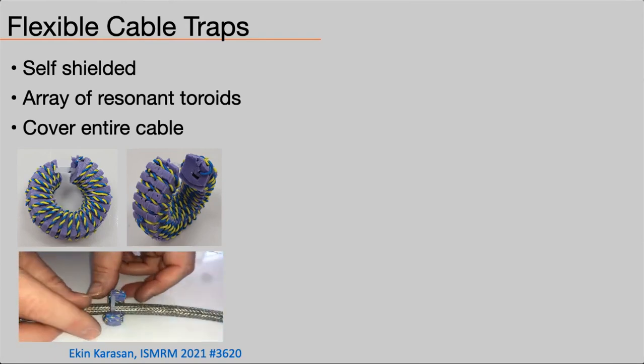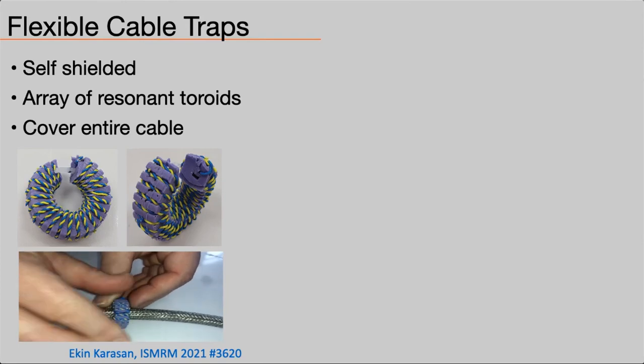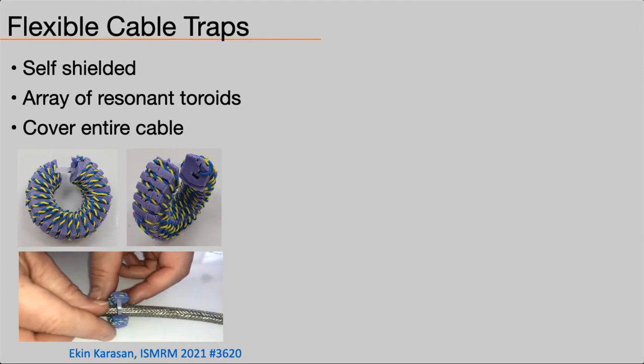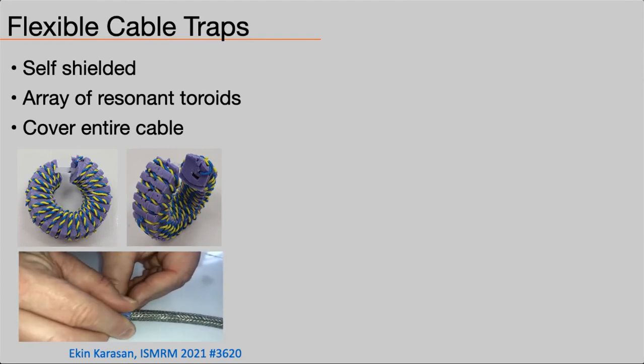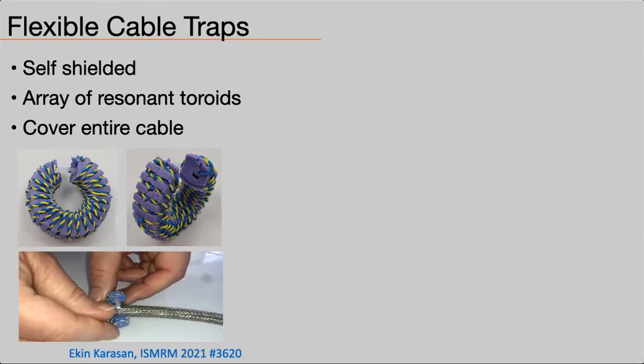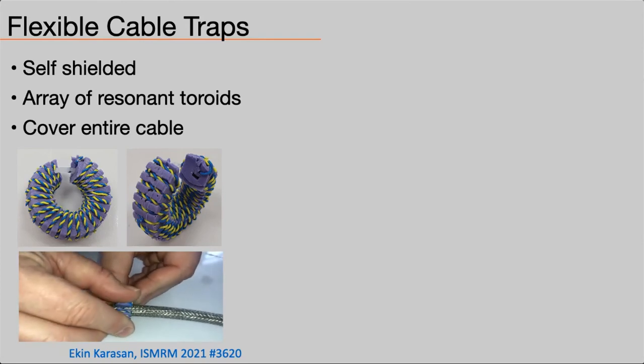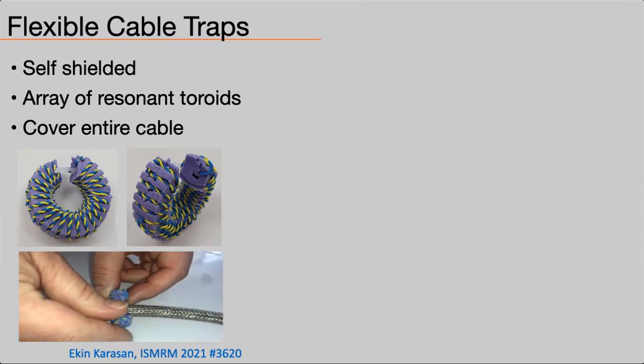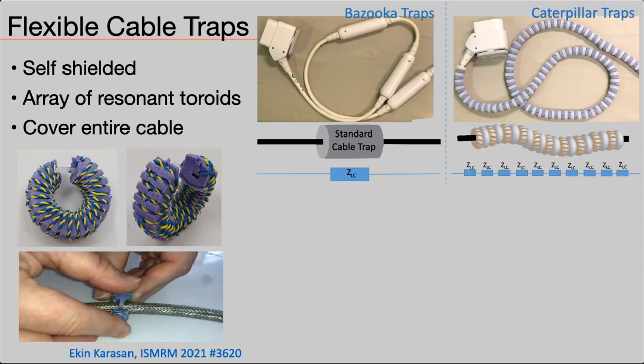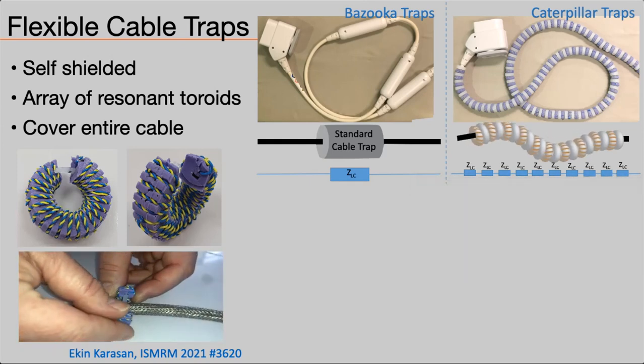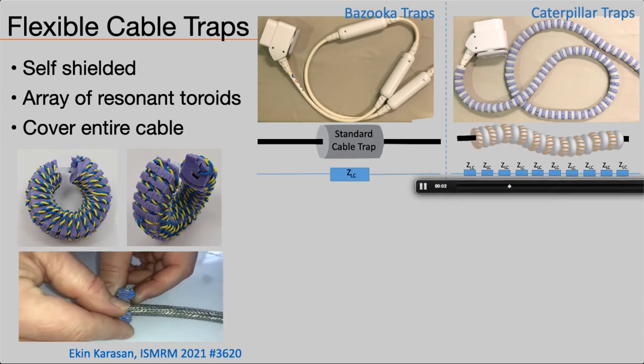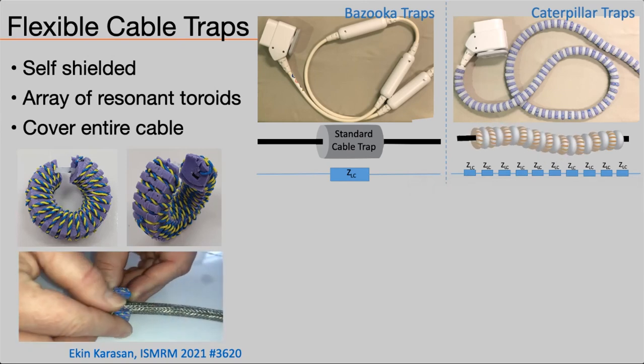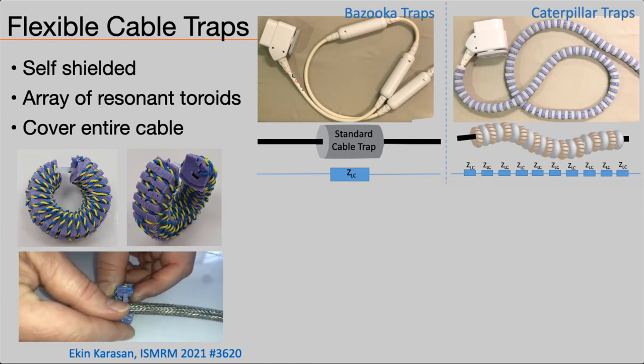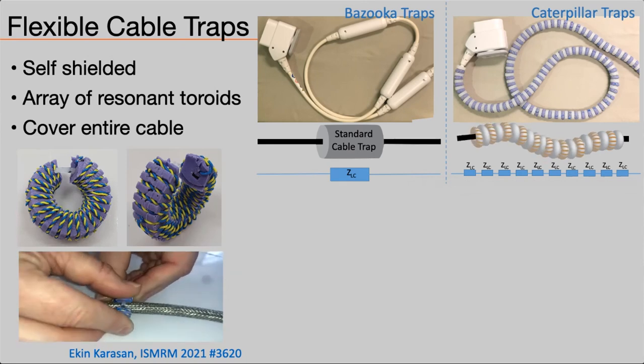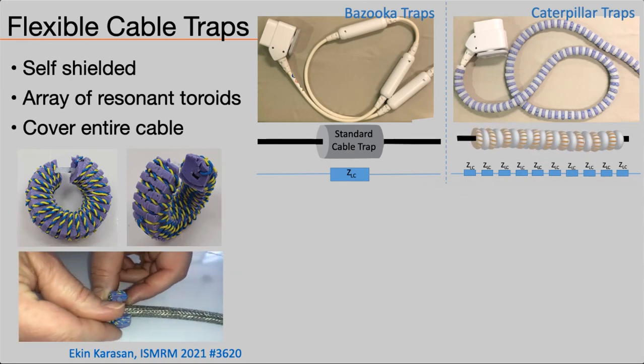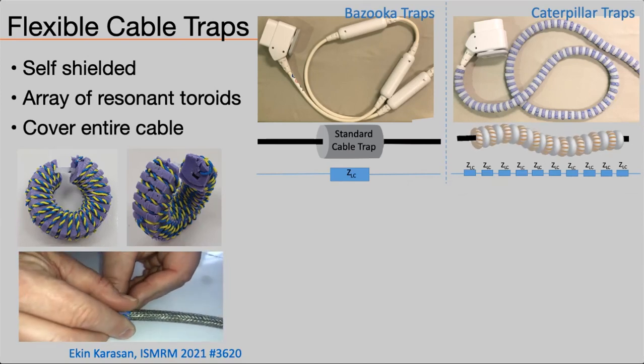So this is Ekin's work, from our group. We've been working over the past two years on a flexible cable trap solution. The idea is to use small toroidal structures that are made resonant via twisted pair transmission line, similar to how coils are made resonant. The torus structures are self-shielded and only weakly interact with each other, so that allows us to cover the entire cable with these while providing high impedance everywhere while maintaining flexibility. You can see the difference between a system cable with traps and our traps. We call them caterpillar traps due to their appearance, they kind of look like caterpillars. Fortunately, these caterpillar traps are RF hungry and can block RF much better than discrete traps.